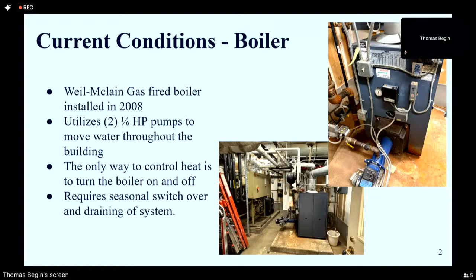Current conditions: right now our boiler is a Weil-McLain gas-fired boiler, installed in 2008, so we're coming up on 20 years old. It utilizes two 1/6 horsepower pumps to move water throughout the building. Currently, the only way to control the temperature during the shoulder seasons, fall and spring, is to turn the boiler on and off. So I have no control over actual temperature—I can just turn it on, warm the building up, then turn it off and let it cool back down. The boiler also requires a seasonal switchover and draining of the system, and once it's shut down and drained for the season, we can no longer provide heat—we're only in cooling at that point.